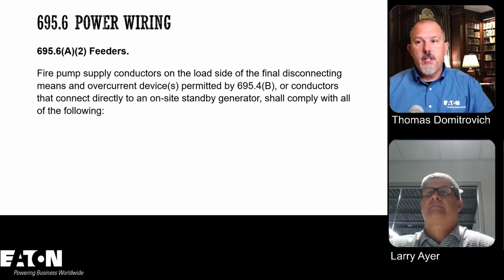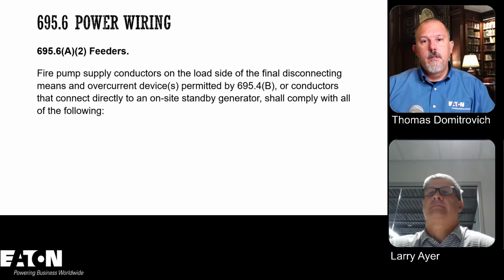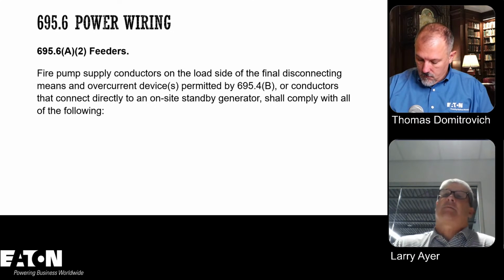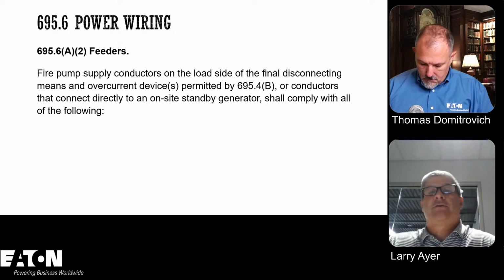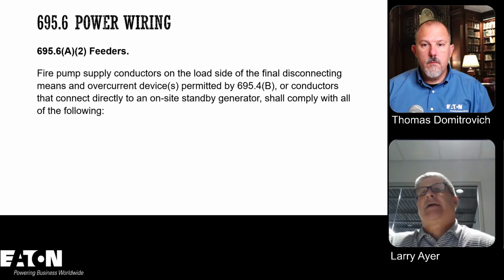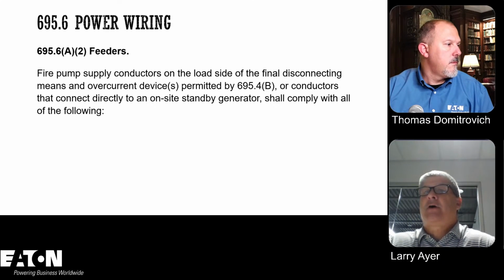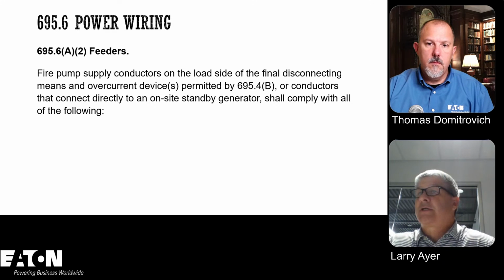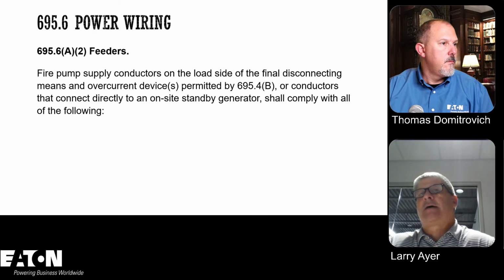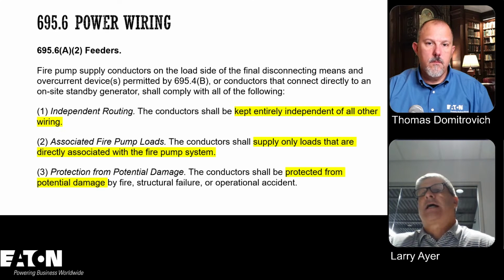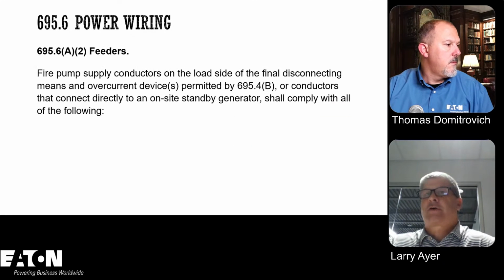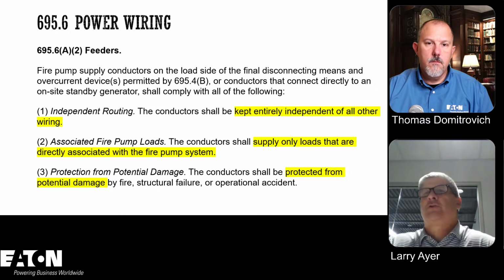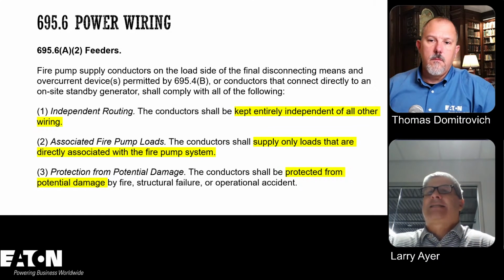Now, when we're dealing with feeders, that means we have an overcurrent device up ahead of us, and we're following 695.4(B). Yeah, so for fire pumps, we have a feeder. It allows us to do something a little bit additional. Yes, you're protecting that where you tap off, but now that allows you to run it through the building if you want. Yep. You could, of course, bury it underneath and come back up through concrete into the fire pump control room. But if you decide that you want to tap off and set your overcurrent device, now you have some additional rules you have to follow.